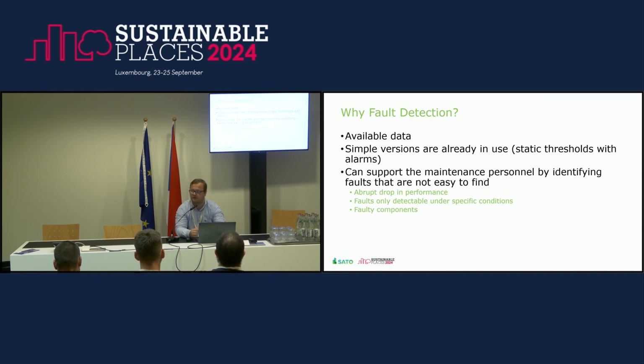That's the threshold-based alarms. So you say, if my system uses more than, as an example, 10 kilowatts of peak power, then we have an issue. It shouldn't do that. That's classic, but it makes it very difficult to actually assess the building in practice, and it is very inflexible to whether this is actually what the building is supposed to do.